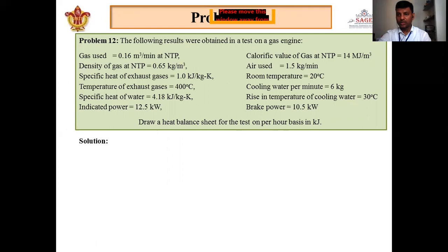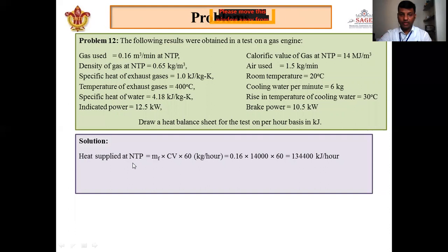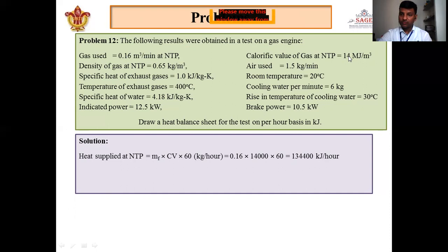We require the total energy supplied to the engine and how that energy is distributed. Heat supplied at NTP equals mf × CV × 60 (to convert from per minute to per hour). So: 0.16 m³/min × 14,000 kJ/m³ × 60 = 134,400 kJ/hour. This is the total energy generated by the fuel when burned over one hour.